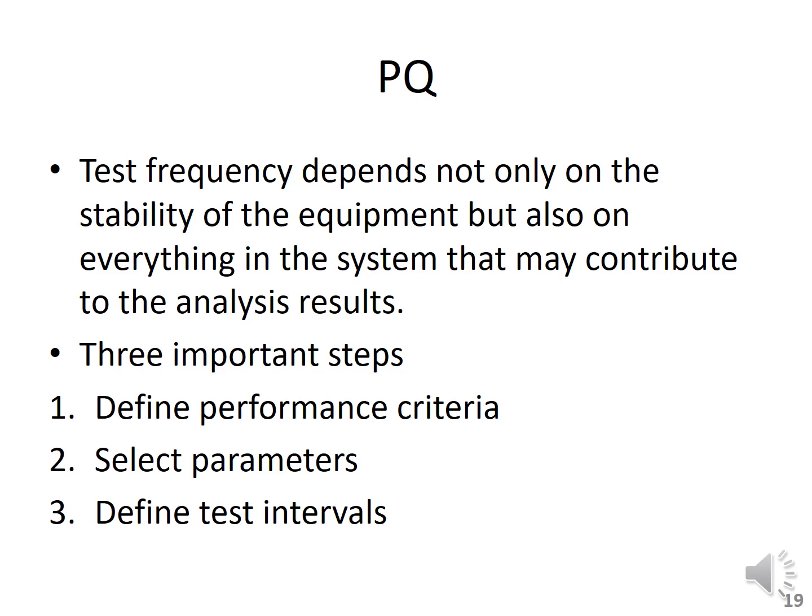And then third, define the test intervals. So whenever the test is required to be performed, or when the test should be performed, you have to define the test intervals, that after this much time the performance qualification tests should be performed. So these three steps are very important. These three factors are very important with reference to the performance qualification.